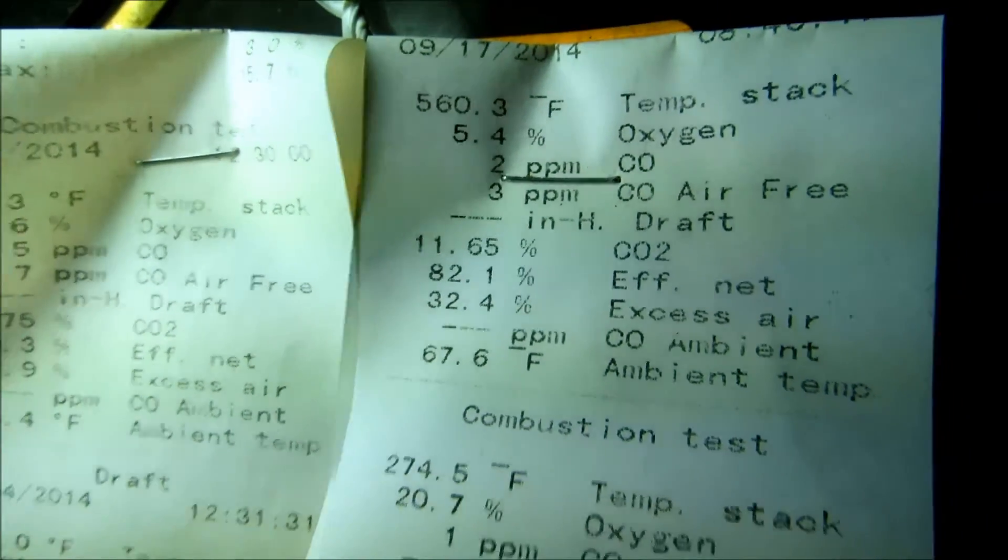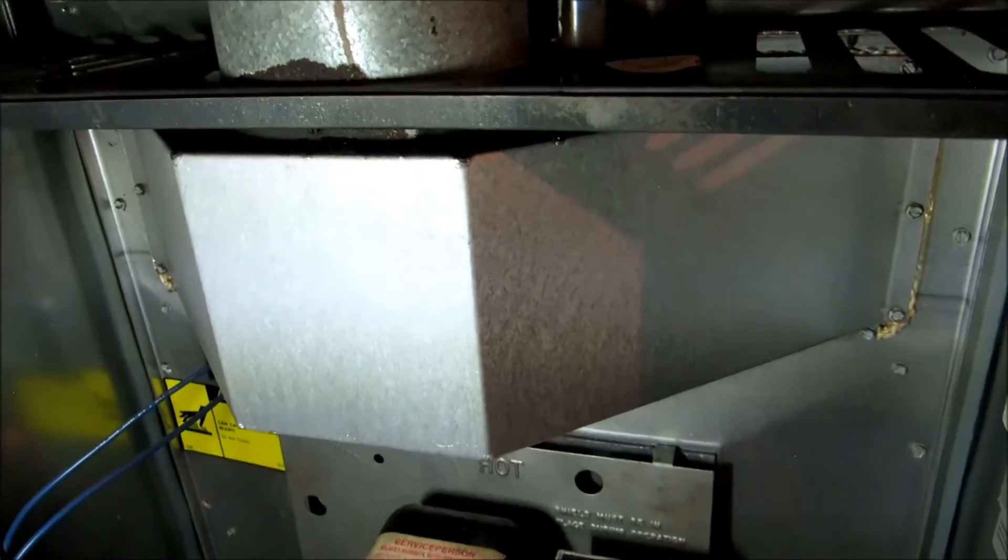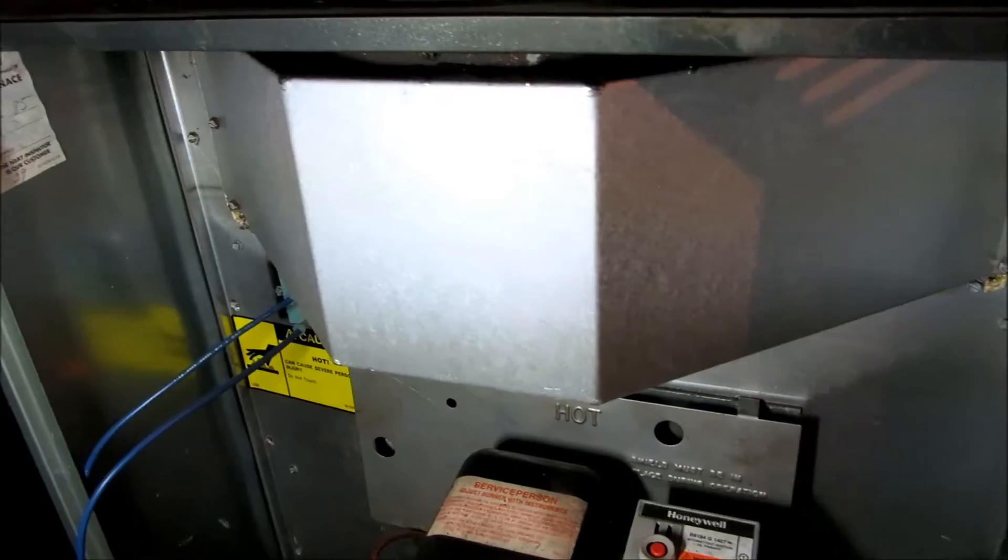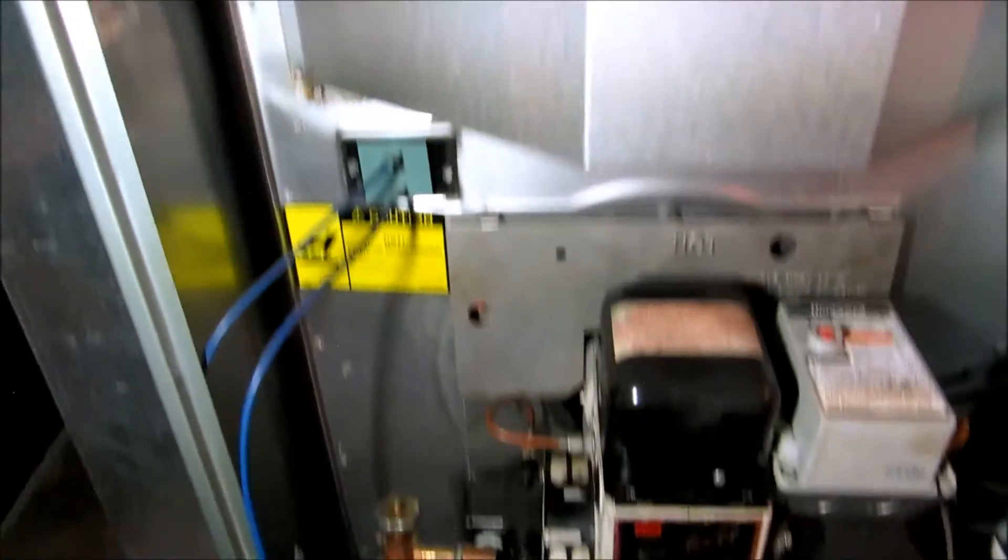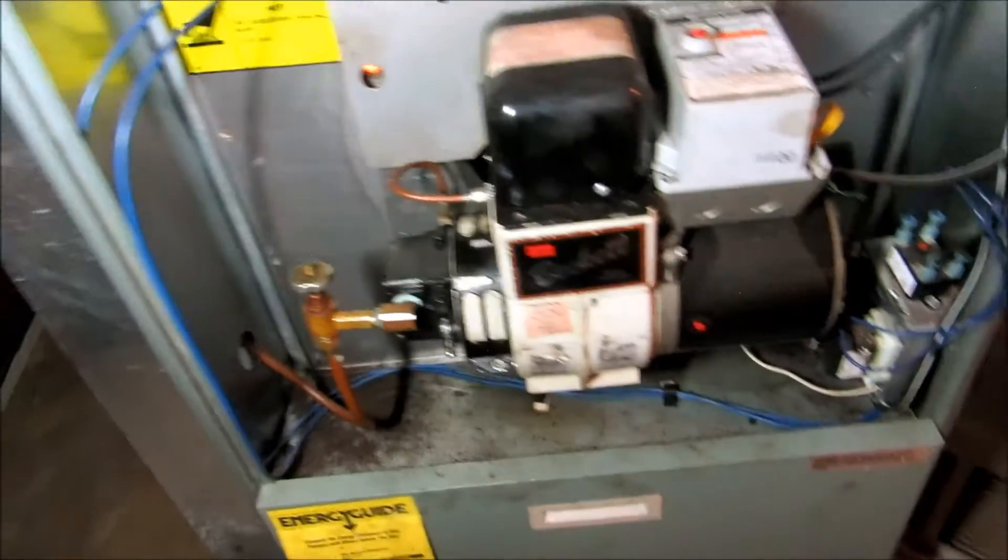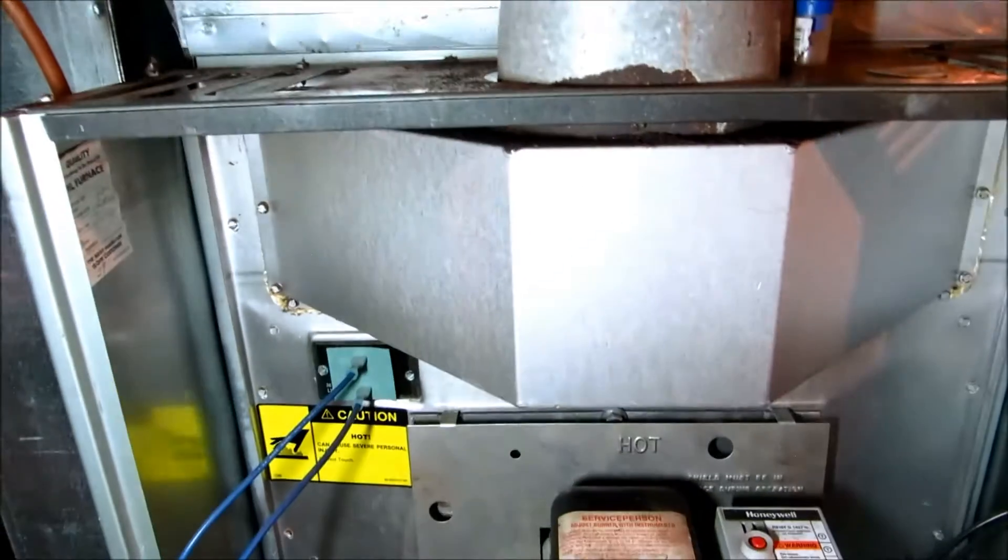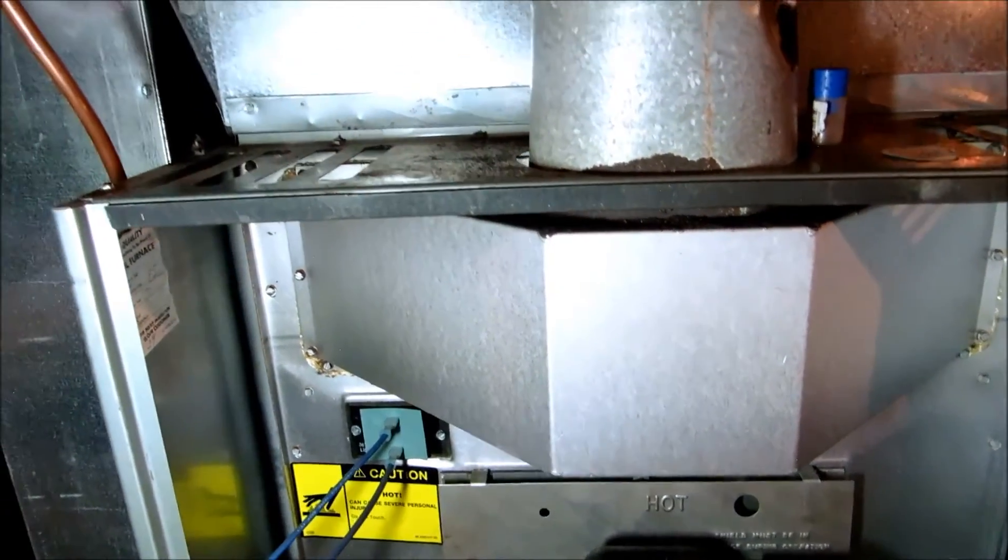Like I said, I like to keep mine below 12, but you just want to have it below smoke. And if I ever took this cover off, you'd see there's a bunch of tiny little like half-inch tubes in there. If this thing ever gets sooted up, it's going to be one hell of a job to clean it. So that's why I like to run them lean, especially these Ruud units. It's hard to clean a furnace. Boiler is much easier.